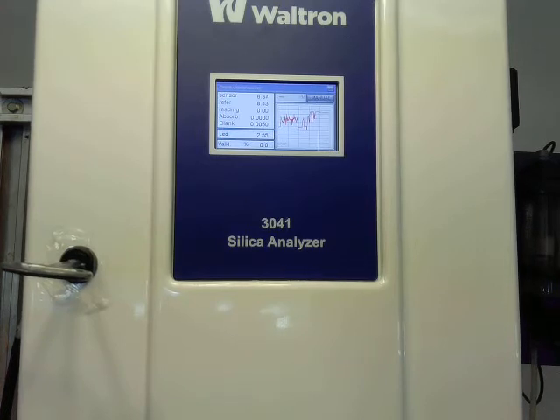So obviously the benefits of calibration are you make sure your analyzer is accurate, but also most problems where we're not adding reagent tend to cause readings of 0. So this gives you a good chance to validate and make sure everything's getting added correctly. Obviously, if we go through a calibration and we don't see any color, we know that there's probably something wrong. But again, when the analyzer calculates its calibration factor, it's programmed to know what a good factor and what a bad factor is. And anything outside that range just says, hey, something's totally not right, and let's take a look at what could be wrong.